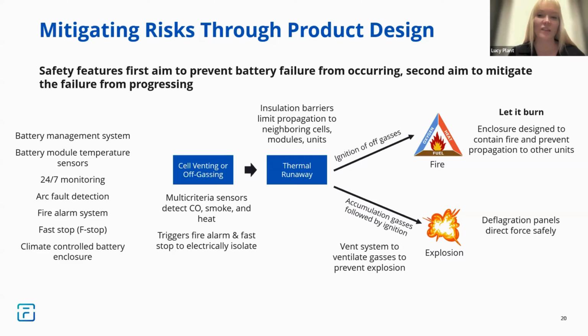The time frame between this initial off-gassing event, the thermal runaway event, and then flames being seen, from our full-scale burn tests, we know is up to 6 hours. So our alarms can go off. We will detect that an off-gassing event is occurring, and therefore we believe that the system is going into potential thermal runaway. You do not want to introduce any air into that system. So you don't want to open up any doors and look inside. You have to leave that system closed and let that continue, hopefully isolating it and preventing it from continuing.